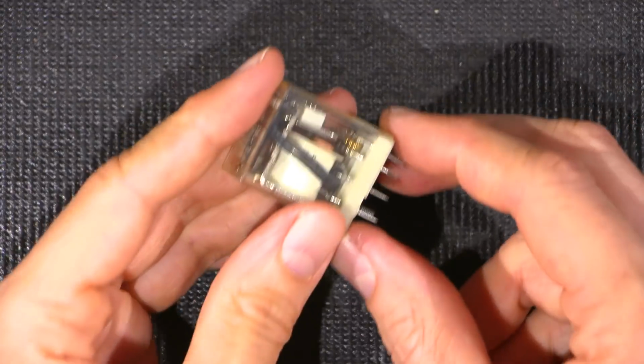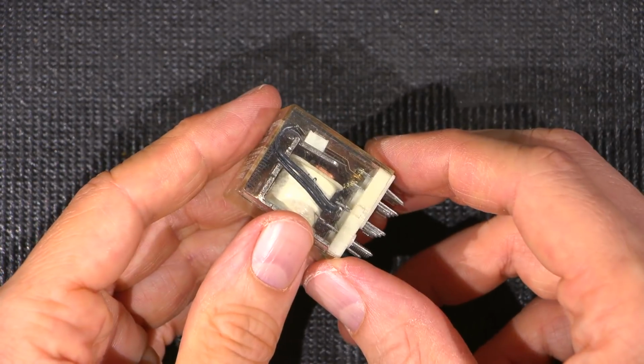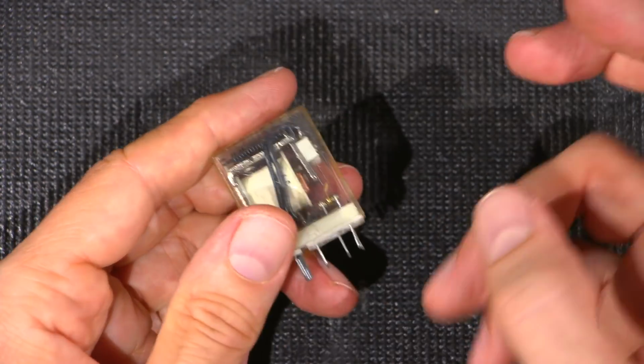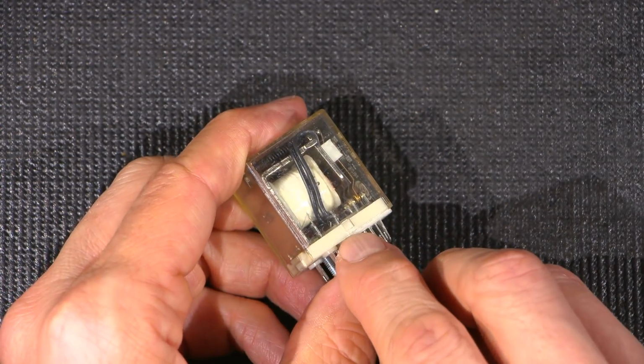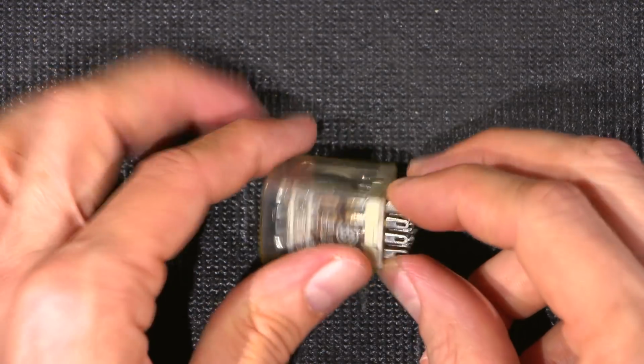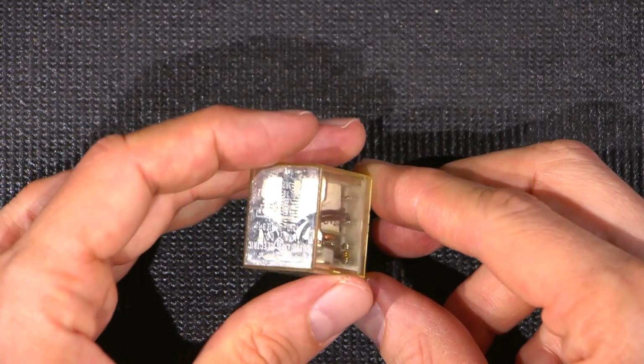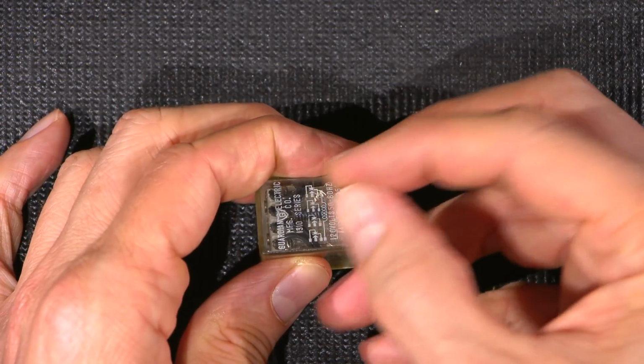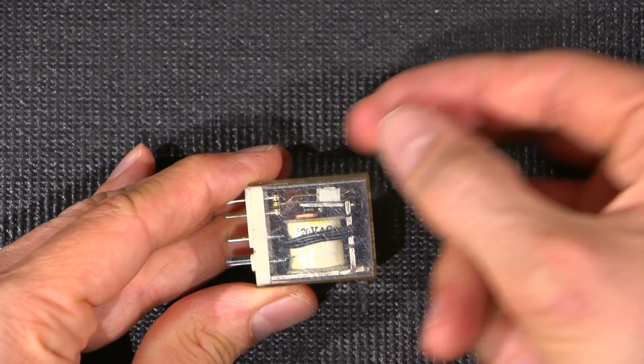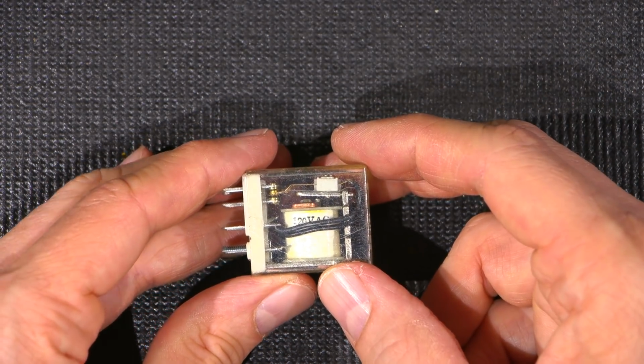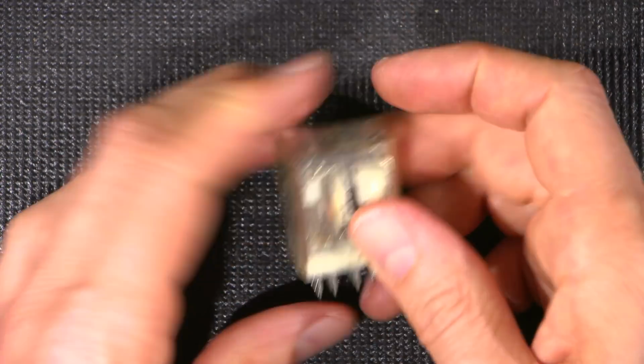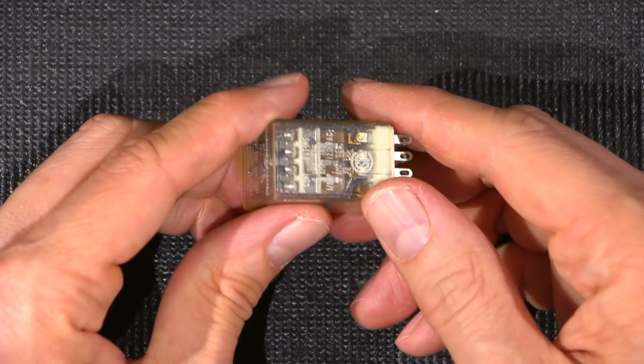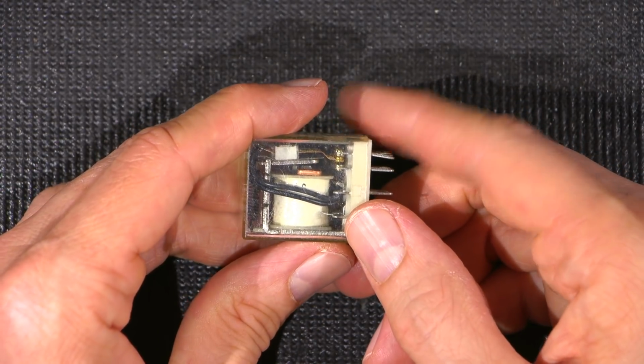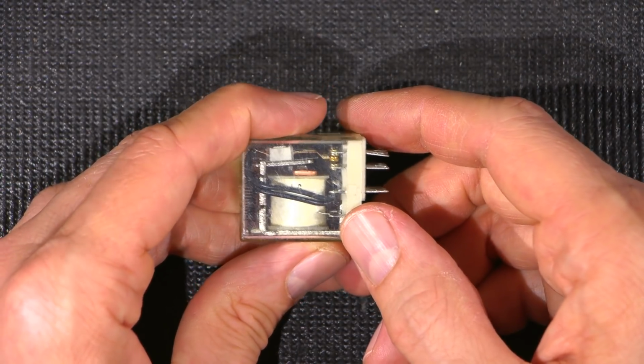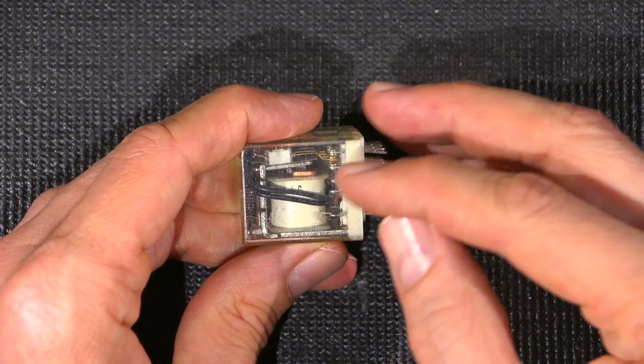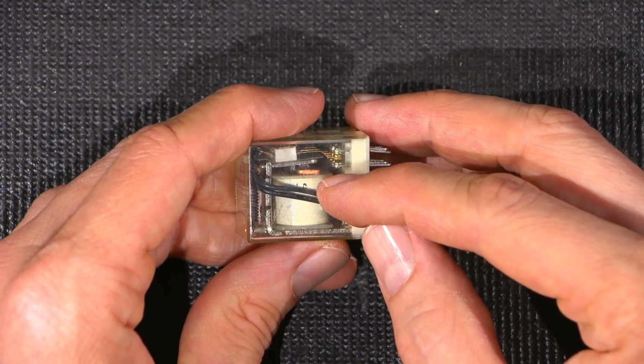Cleaning relay contacts is actually very easy in a case like this. So when you have a relay that you can remove the case from, you just pry the tangs up and then the plastic cover comes off. I'm sure you've all done this at some time. And then you just remove the spring and you can actually take the whole front area right out. Now, when you're dealing with contacts like this, usually relays of this size are used in an application where there's current being passed through the contacts. And relays self-clean their contacts as they spark.